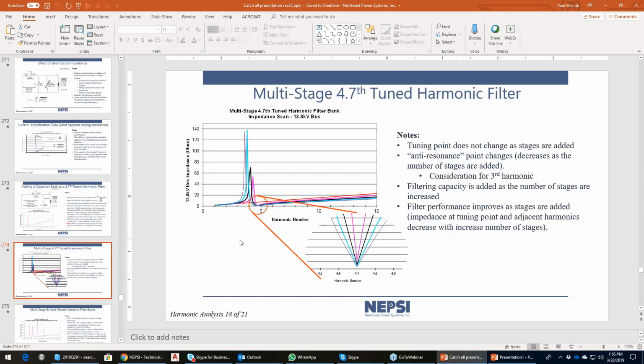Why was the tuning point set at 4.8 or 4.9? I think I've already answered this. What we're trying to do is avoid resonance at frequencies above the 5th, because there could be harmonic currents at values above the 5th harmonic. So we always pick a value below the 5th. As I showed in the presentation, the further you get away from the 5th harmonic, the less harmonic current the filter, or that detuned filter, whichever you want to call it, will take in. But as I showed during the presentation, even a 4.2 harmonic filter or detuned capacitor bank will pull in harmonic current.